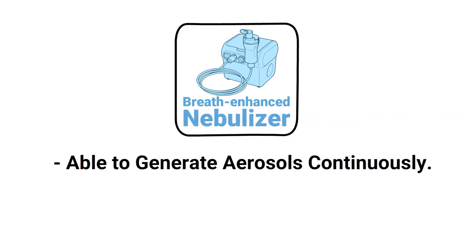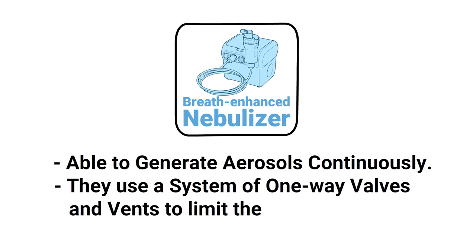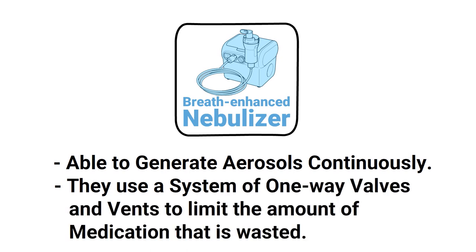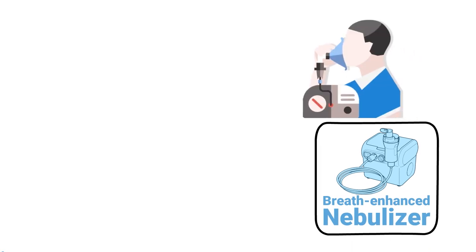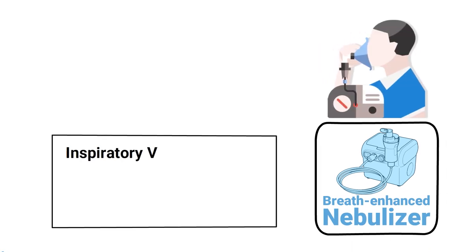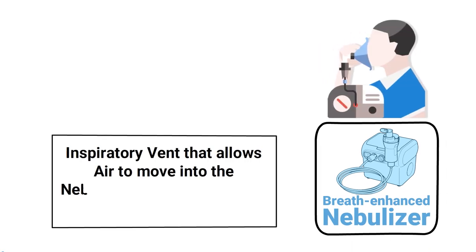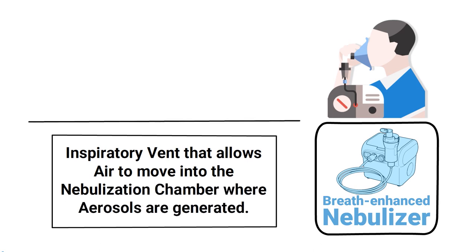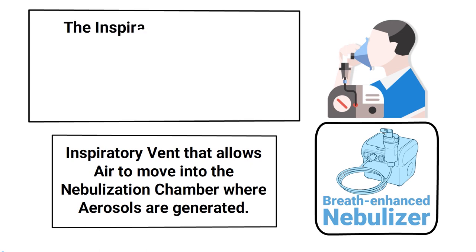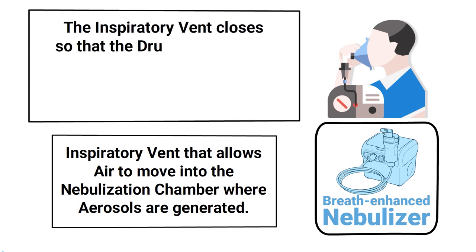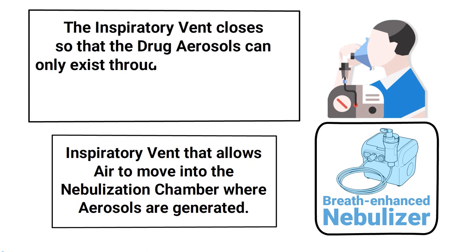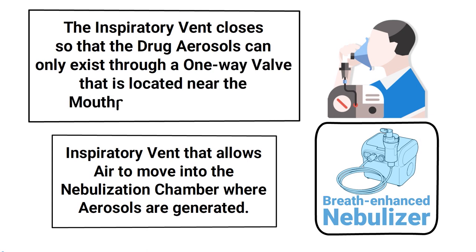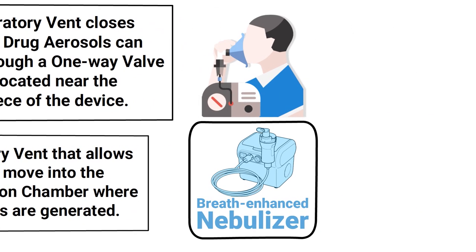Breath enhanced nebulizers generate aerosols continuously, and they use a system of one-way valves and vents to limit the amount of medication that is wasted. When a patient takes a breath in, there is an inspiratory vent that allows air to move into the nebulization chamber where aerosols are generated. Then as the patient exhales, the inspiratory vent closes so that the drug aerosols can only exit through a one-way valve located near the mouthpiece of the device.